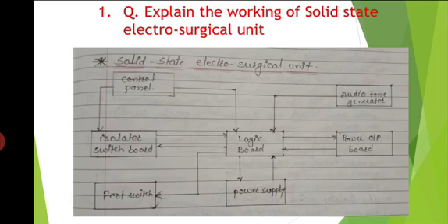The isolator switch provides isolated switching control between the active hand switch and the rest of the unit. Logic circuits are used to receive external control signals and to operate the isolating relays, which give visual indication and determine the alarm conditions. The logic circuit receives information from the foot switch, finger switch and alarm sensing points.